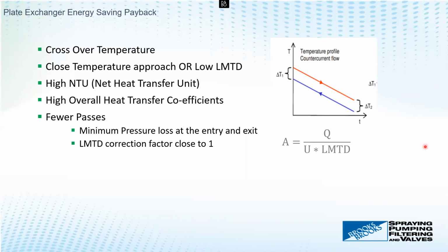If you see this graph, the hot side in is here, hot side out is at the end, cold side in is at the beginning of that blue line from the bottom, and then the cold side out. So crossover temperature means that the outlet temperature of the hot side is lower than the cold side outlet temperature. That's the type of thing we need when there is a heat recovery application.